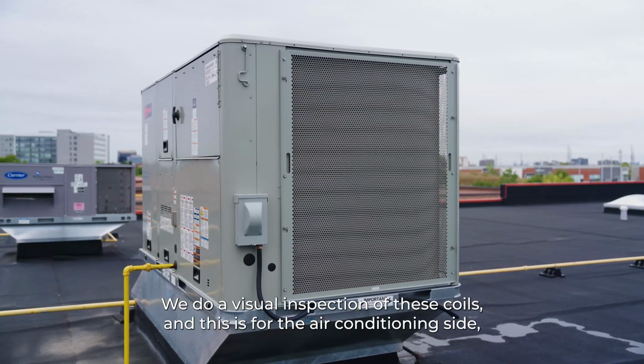We do a visual inspection of these coils, and this is for the air conditioning side, making sure that the fins on the coils and everything is the way it was from factory. They're not bent, no birds have hit them, because that will affect the efficiency of the cooling capacity on these units if the fins are bent in any way, shape, or form. If there was a situation where they were bent, we have a set of combs that can straighten out the fins, providing we do a quick visual inspection, make sure there's no damage to the actual refrigerant lines within those coils, because that's what provides all the cooling effect.